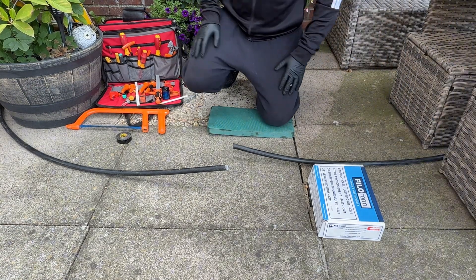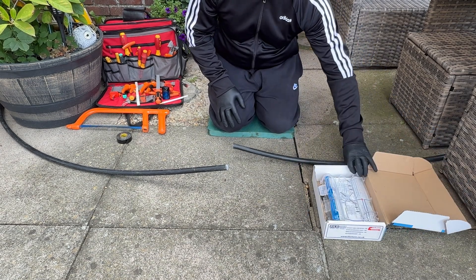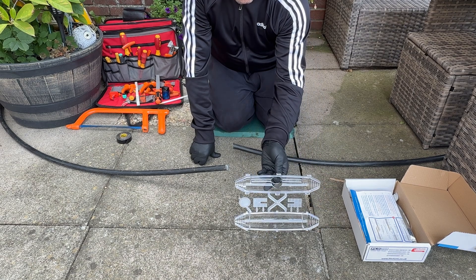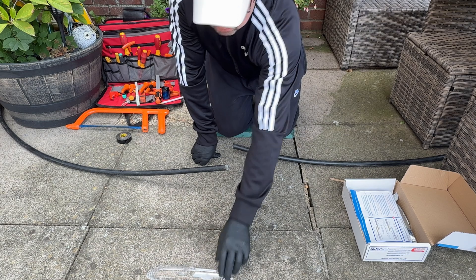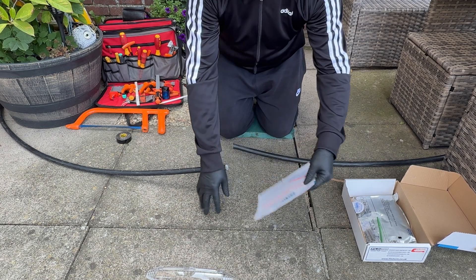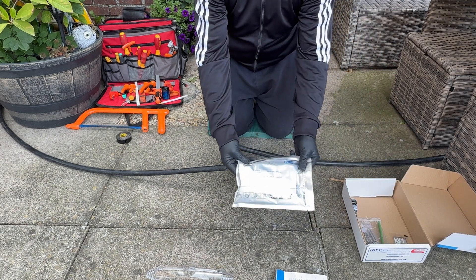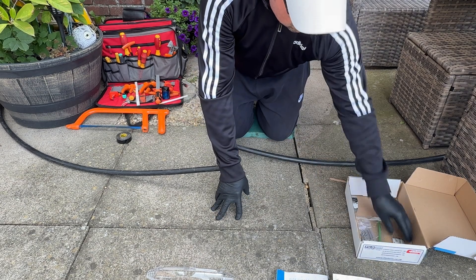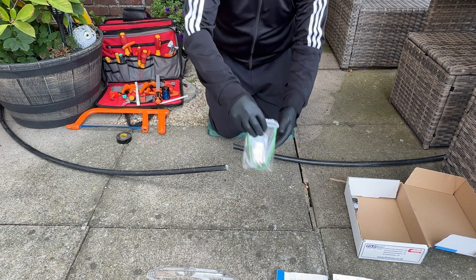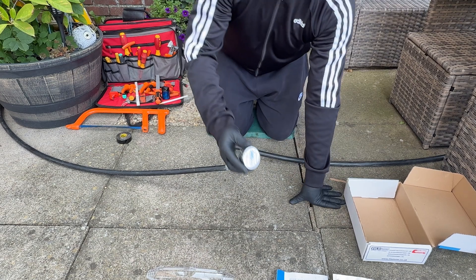Hi guys, today I'm going to be showing you how to joint two pieces of SWA together for an underground joint. This is a resin-filled joint, comes as a complete kit. Inside we have the joint shell itself, some instructions — you need to look at them, it tells you how much abrasion to make on the outer sheath of the SWA cable and when the inner core should be jointed. Resin — make sure you wear gloves whilst using that. That's a set of gloves that actually comes in the box. earth strap kit and a roll of tape.